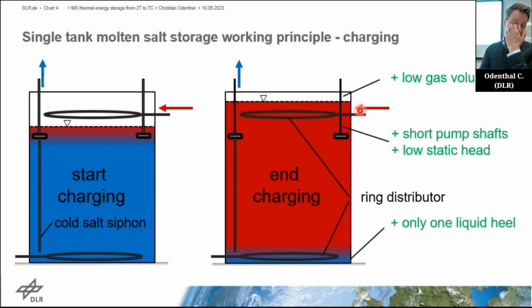There are some advantages of this concept. The first one is with the two tanks, you have obviously about 50% of the volume is unused. You have a high volume of gases, which you have to manage. And in that case, this volume is clearly reduced. Another aspect is in the two-tank system, you always have to completely empty the tanks. So the pumps need to have very long shafts. And in this case, since you always have some liquid level in here, you can use short shafted pumps, which are much less costly.